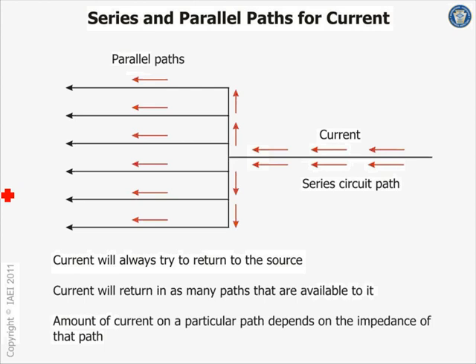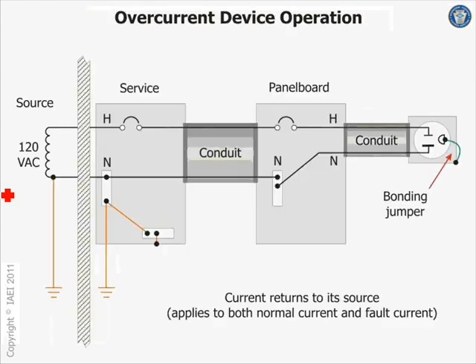That's why we don't want you to bond the neutral other than at the service. Same thing, guys, for the grounding and bonding. When you ground and bond everything together at both ends, you are creating parallel paths. So the current will go in each and every one of these paths. And I keep emphasizing the words normal operating condition, when the power system is running and the air handling is up and running, and abnormal condition, when the circuit is in a ground fault condition or in a short circuit condition. Okay, here's the overcurrent device.